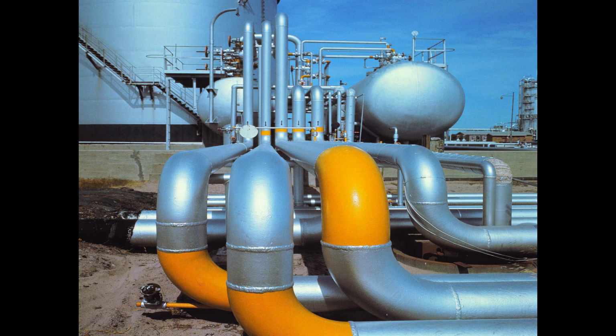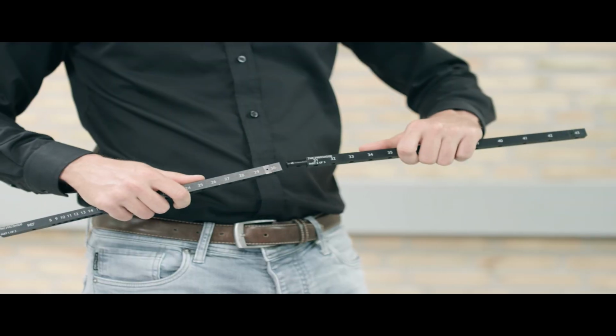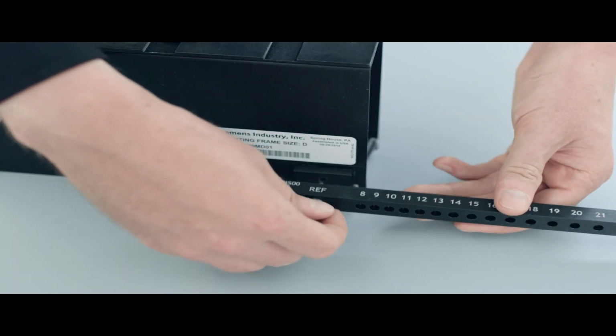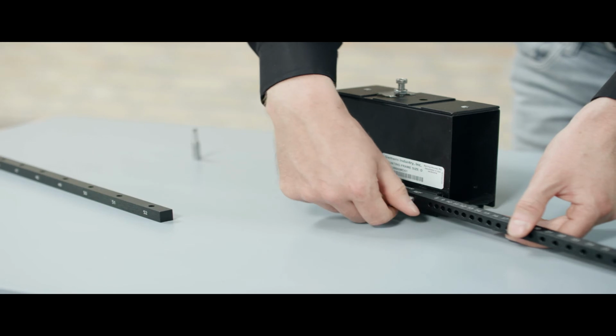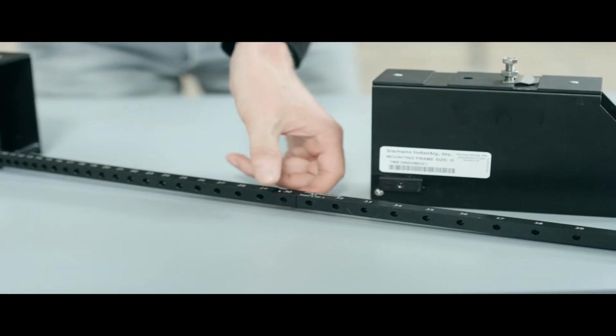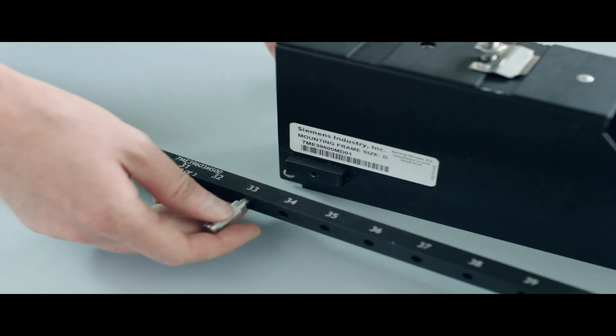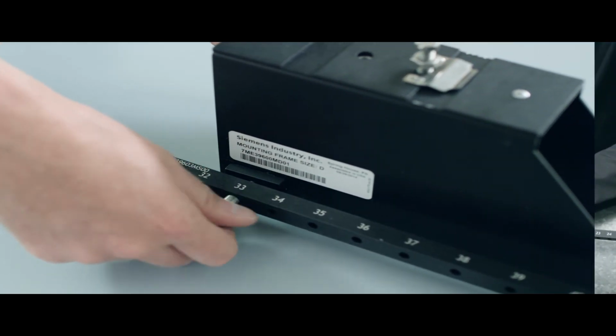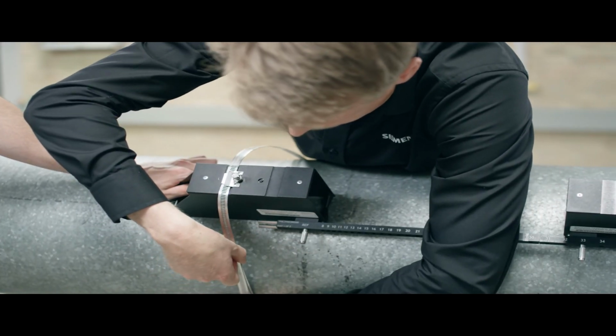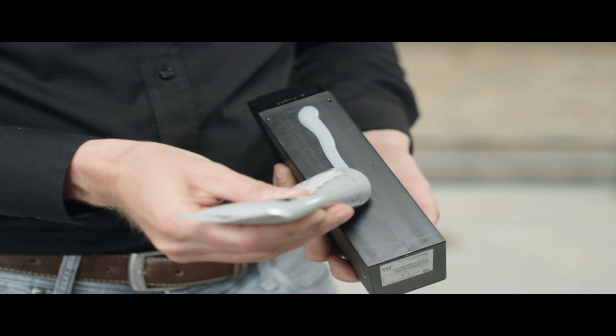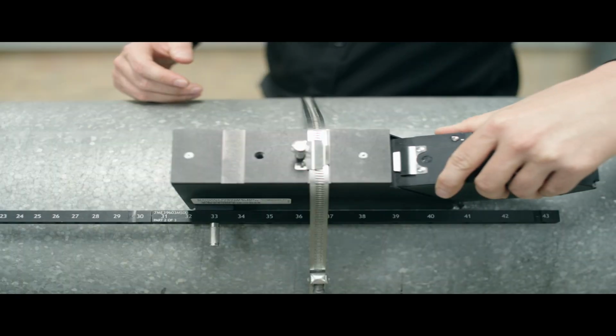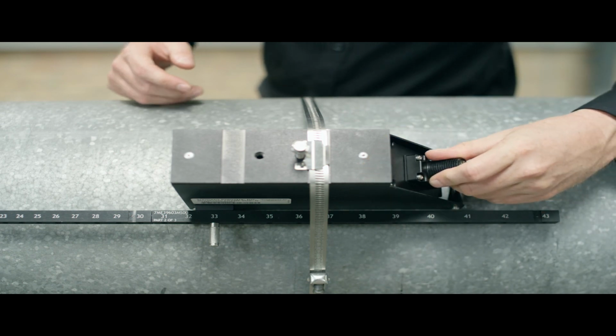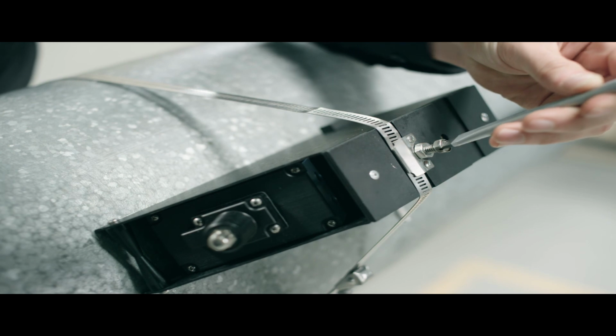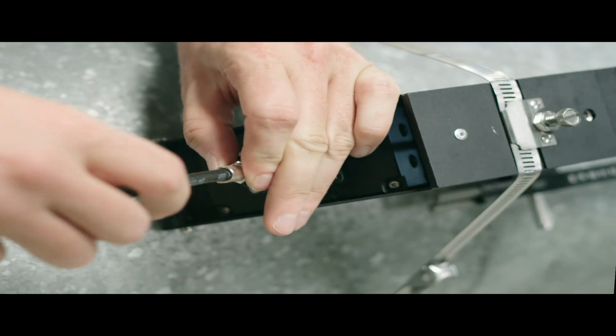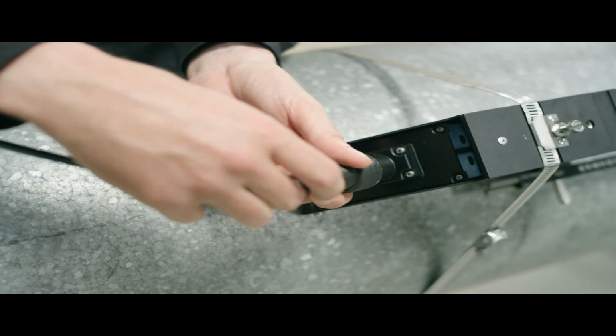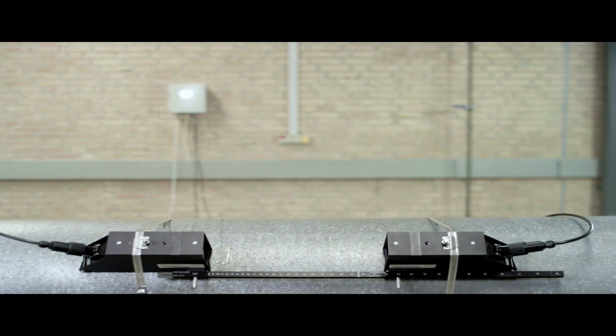Once you've determined the location for your sensor installation, you can prepare the sensors for mounting. Attach one mounting frame to the reference position of the spacer bar and attach the second mounting frame to the number index the meter provided when you programmed it. Strap the frame and bar assembly to the pipe at your chosen location. Next, apply a thin bead of couplant to the sensors and carefully insert them into the frames and up against the cross brace. Tighten the sensors with the overhead bolt and then attach your cables, noting the flow direction. Your sensor mount is now complete and ready for operation.